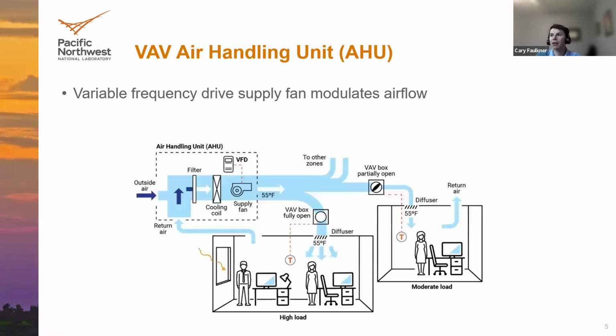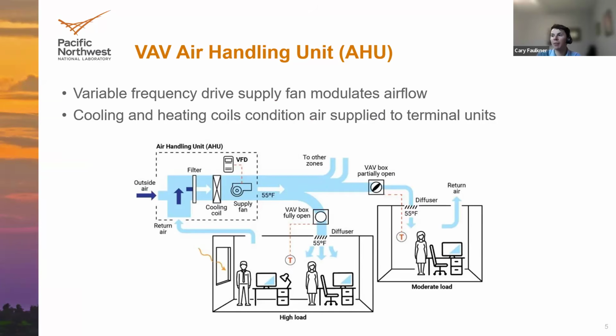So let's break it down to the key components of a VAV system. First, you have the air handling unit, or the AHU. This is going to include your fan, which for a VAV system is going to be some sort of variable frequency drive fan that is able to modulate the airflow and provides that variable airflow aspect of the VAV system. Typically at the air handling unit, you're also going to have cooling and heating coils to condition the air supplied to terminal units.